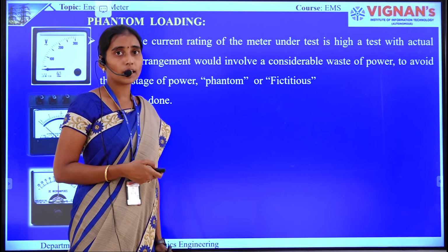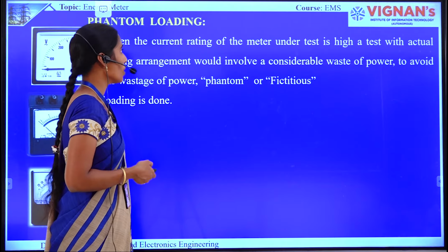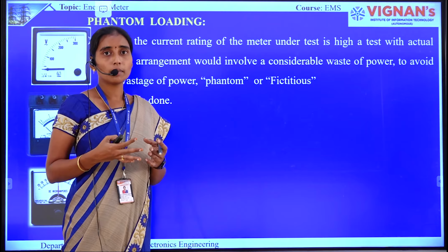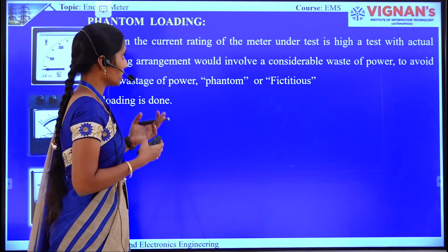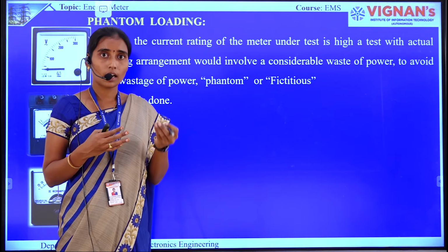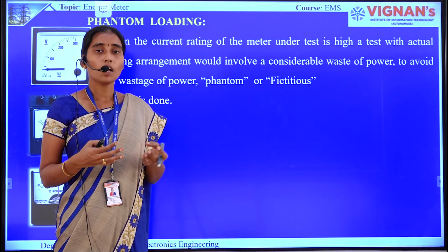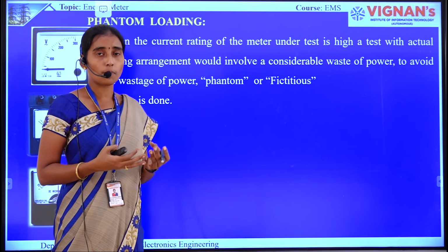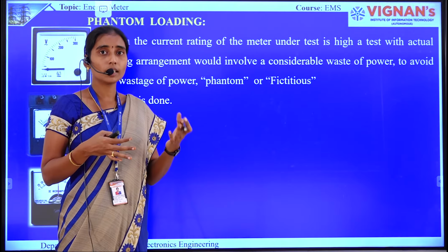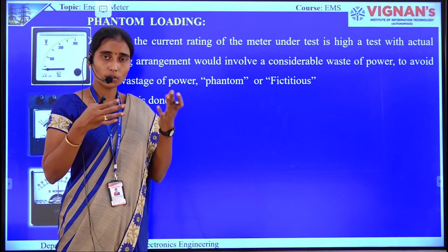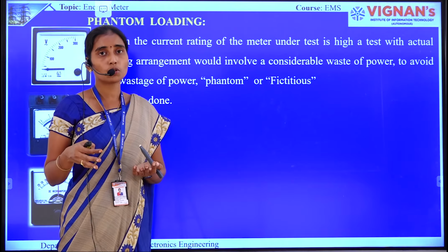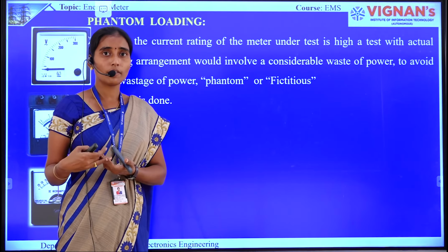And coming to phantom loading. In general, when you are testing a meter, in order to test it we need to load it. When the meter under test has high voltage or high current ratings, general testing is not possible because it requires a large amount of current as well as a large amount of voltage, which in turn wastes power. So in order to test the instrument, we need to subject a large amount of voltage as well as current through it, which in turn is wastage of power.